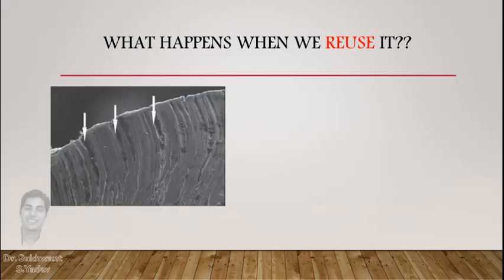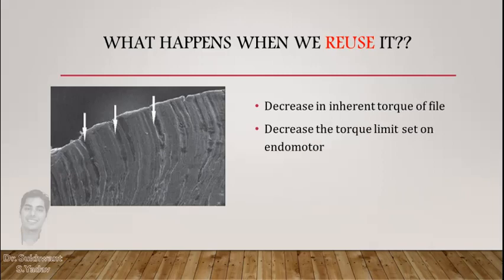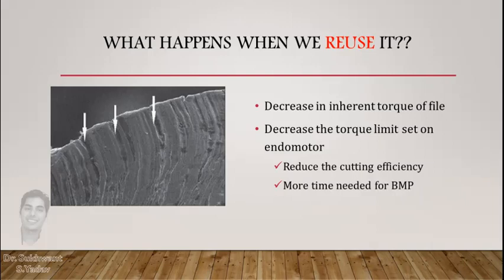What will happen to torque when an instrument is used again? During canal preparation, the instrument undergoes stresses which lead to surface cracks. These deformities reduce its capacity to bear torque, so the torque limit set on the endomotor should be decreased. But this reduces cutting efficiency and more time is needed. Eventually, its capacity decreases to a level where it will fracture — this is known as cyclic fatigue fracture.